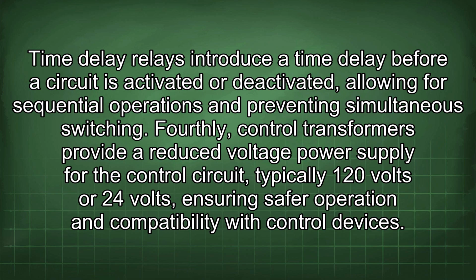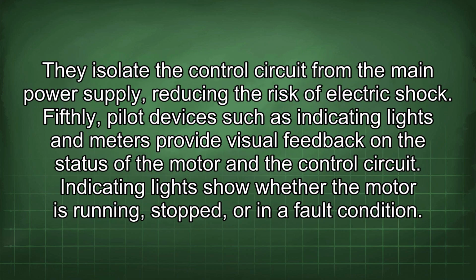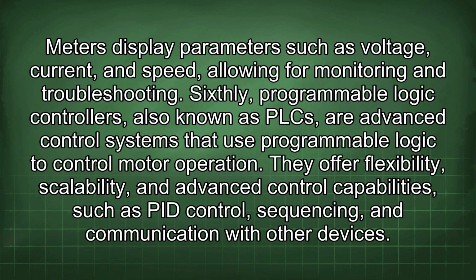Fourthly, control transformers provide a reduced voltage power supply for the control circuit, typically 120 volts or 24 volts, ensuring safer operation and compatibility with control devices. They isolate the control circuit from the main power supply, reducing the risk of electric shock. Fifthly, pilot devices such as indicating lights and meters provide visual feedback on the status of the motor and the control circuit. Indicating lights show whether the motor is running, stopped, or in a fault condition. Meters display parameters such as voltage, current, and speed, allowing for monitoring and troubleshooting.